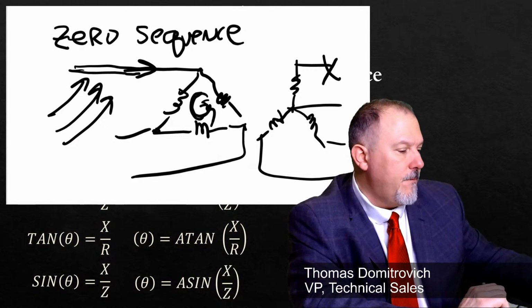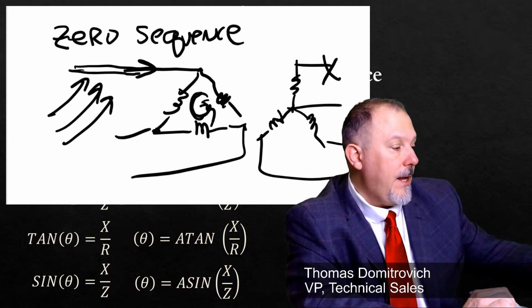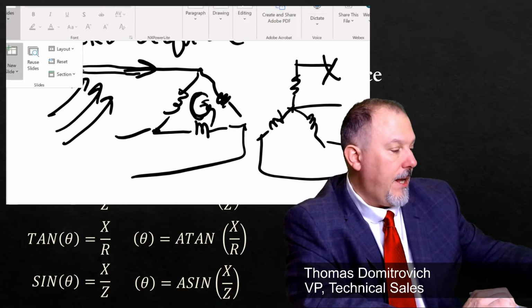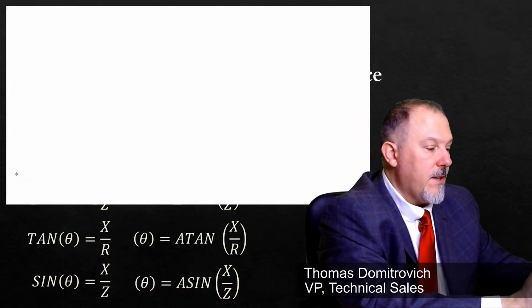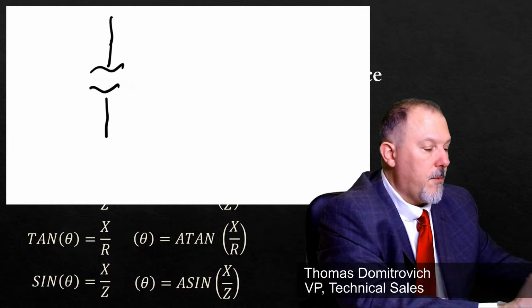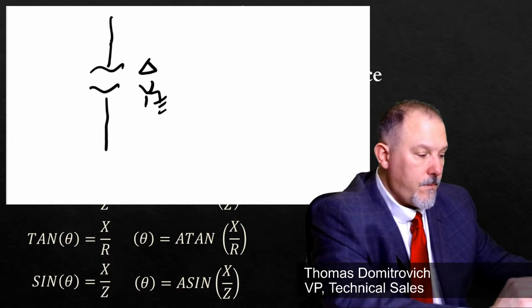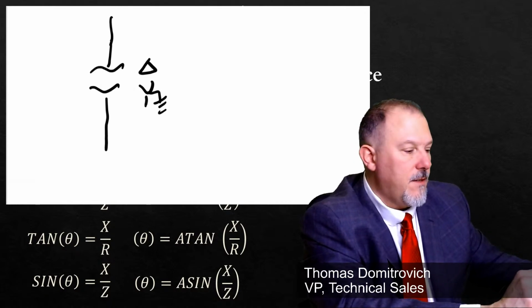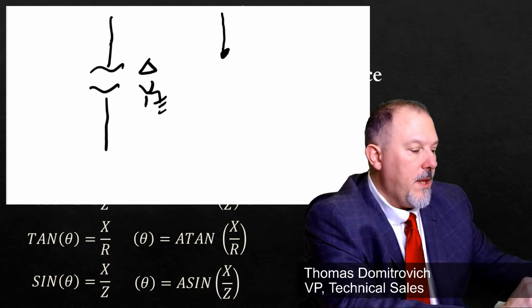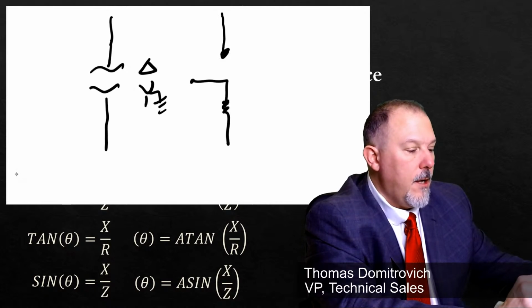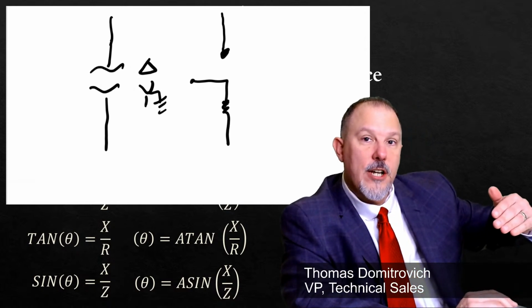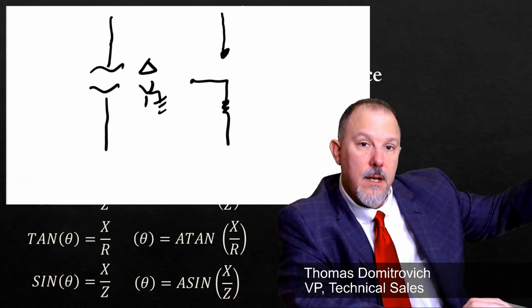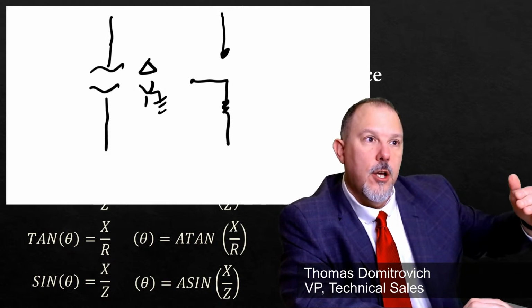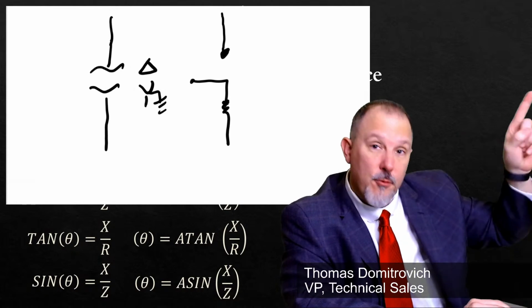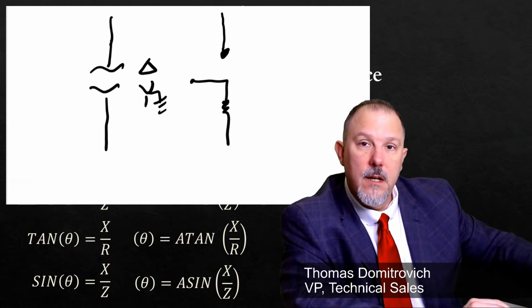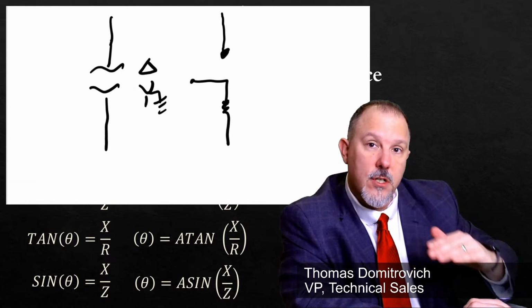If you think about how we draw the circuits, I have a system that looks like this, and I have a transformer, and it is a delta Y ground. My equivalent impedance of this will be this. I don't have to worry about any impedances ahead of this transformer, because the ground fault currents won't flow through those impedances, because the delta is an isolation from the rest of the circuit.